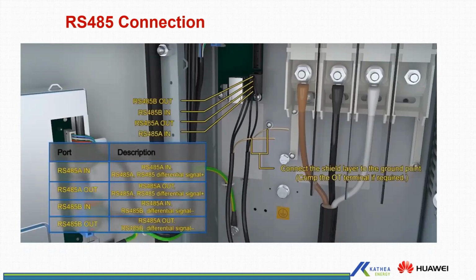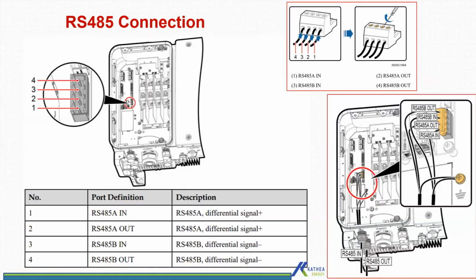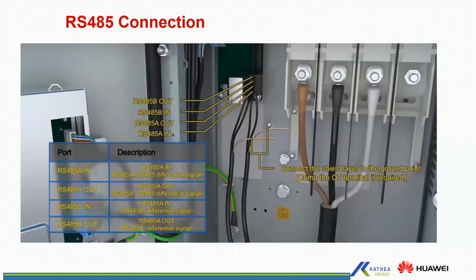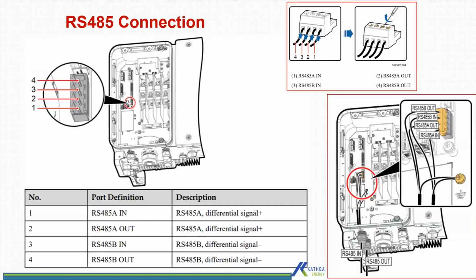So you have RS485 A in, A out, B in, and B out. When you are daisy chaining, those are the pin layouts for the 50 and 60 KTL. Next to the RS485 connector, there is an earth point for the comms channel. Then you just need to wire your RS485 shield to the earth terminal. This is basically how the plug looks. You can remove the plug, terminate your cables, and then plug it back into the inverter.